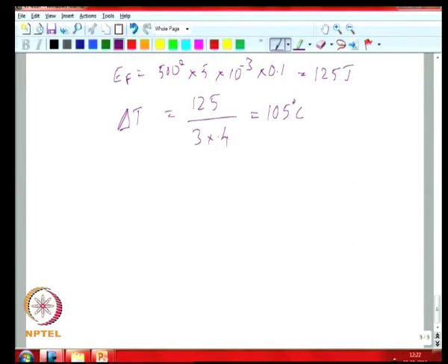The other thing that you could do is maybe you could see if your fault current level can be reduced below 500 amps, which would give you again margin in your temperature. Again, it may not be possible to change it under your source impedance, because it may not be directly under your control. So, your first option was to see if T_F can be reduced. The second was whether I_F magnitude can be reduced.